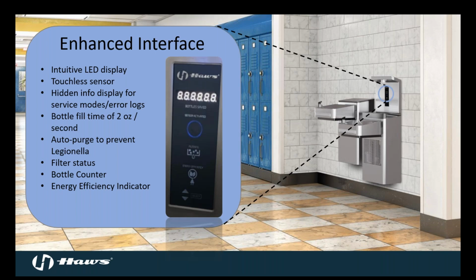There's also an energy efficiency indicator on these displays, which goes into effect 1 hour after the unit doesn't detect any motion or light. This is ideal for anywhere that shuts down, like an office building at night. If there's no motion or light for an hour, it stops chilling water, saving wear and tear, then turns back on and begins chilling immediately when someone comes in and turns on the lights.